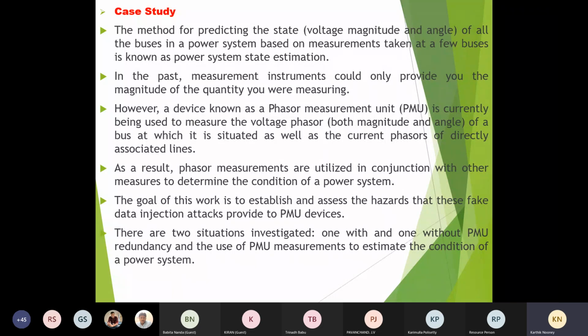That means if you are getting fault data, the CB has to open at a particular time interval, and if that breaker opens prior to that or after that, it results in malfunction of the breaker. Like that, there are many instances where you can quote examples where, for relaying or breaker switching operations, if the data is not exact, the breaker doesn't know. Simply it is a switching action that depends upon the sensing device, the relay. That's why we have to access those values beforehand and give the values precisely, the information to the end user, that means substation people or the breaker, so that they can isolate the faulty system exactly.